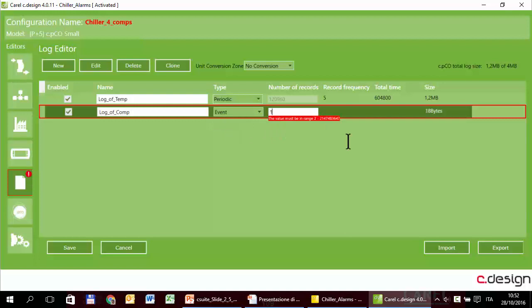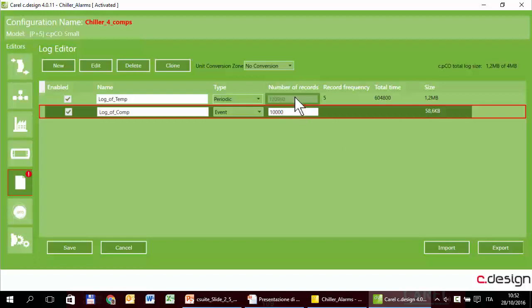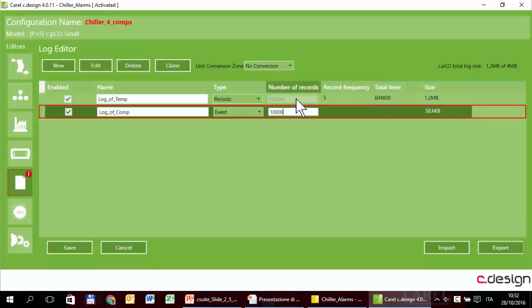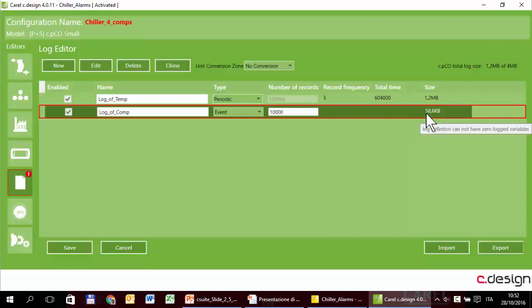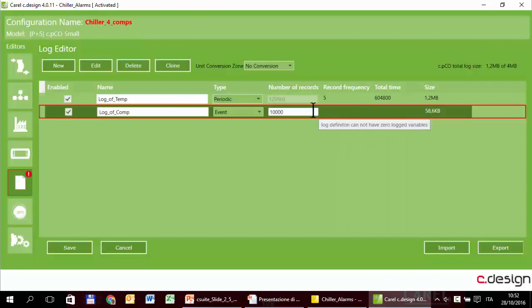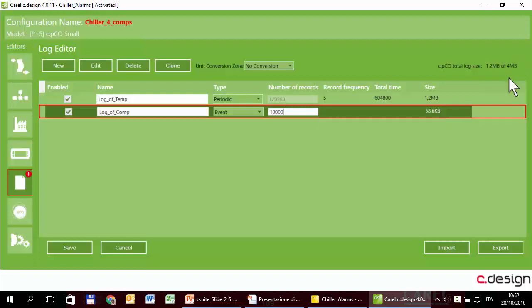How many records? In the previous case the number of records depends on the total time and the sample time, and the system automatically indicates the total number of records. In case of event we have to specify it manually. So these 10,000 records take about 60 kilobytes. These two logs occupy 1.2 megabytes out of the four that are available.